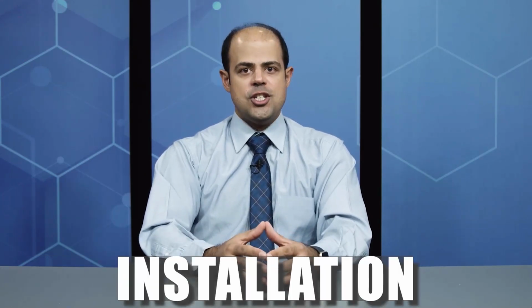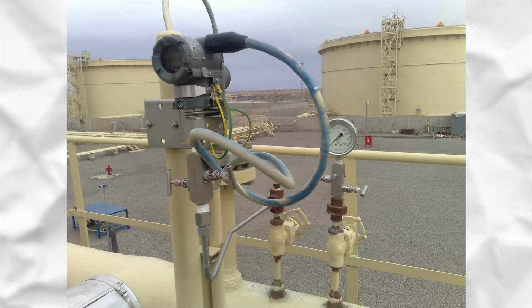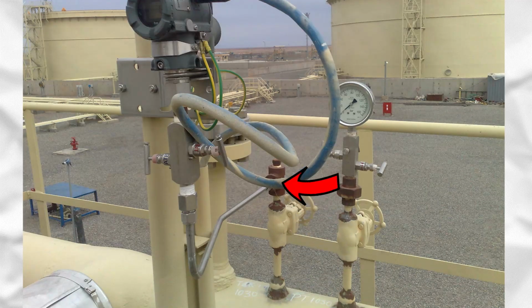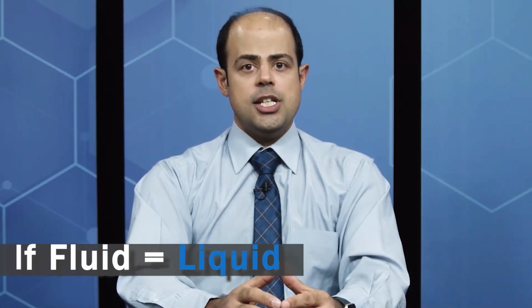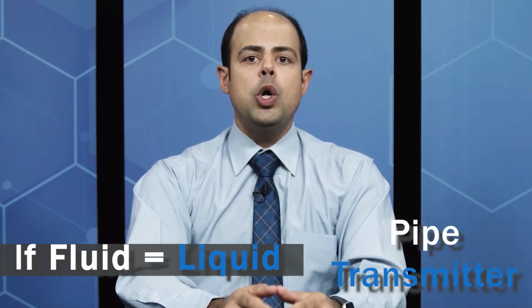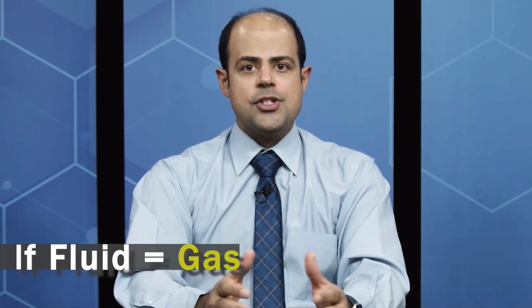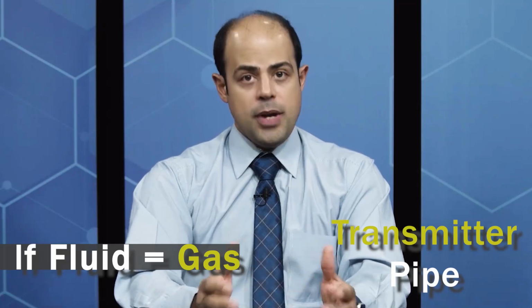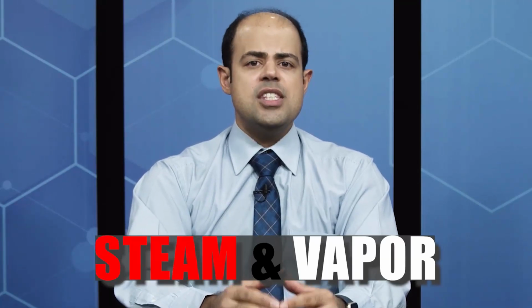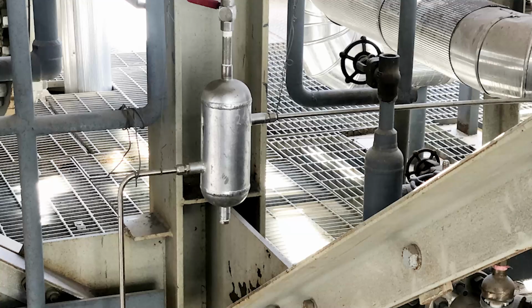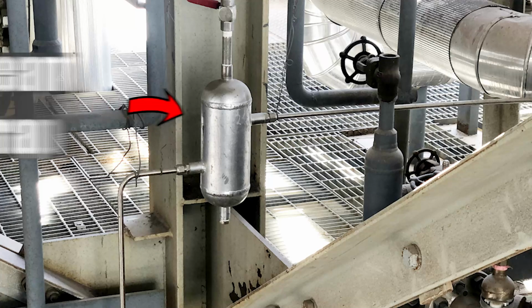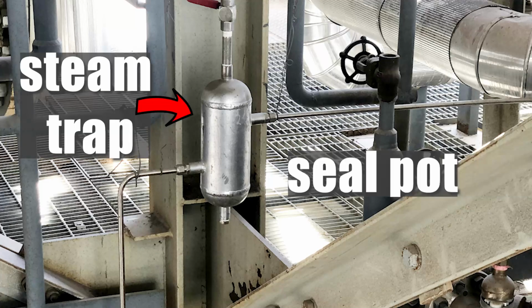Let's put calibration aside and deal with their installation. In most applications, pressure transmitters are installed further from the pipe. With the help of tubing from the tap on the pipe, we are able to install the pressure transmitter. Be notified that if the fluid is liquid, you must locate the transmitter lower than the pipe tap, while for gas services, we'll locate it at a higher elevation. Sometimes you deal with steam and vapor. Since this fluid is likely to be condensed, you should use a steam trap, also known as a seal pot.